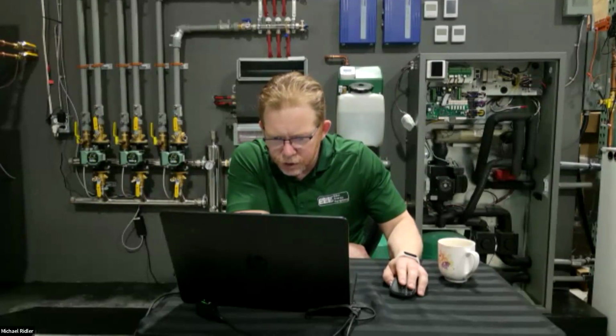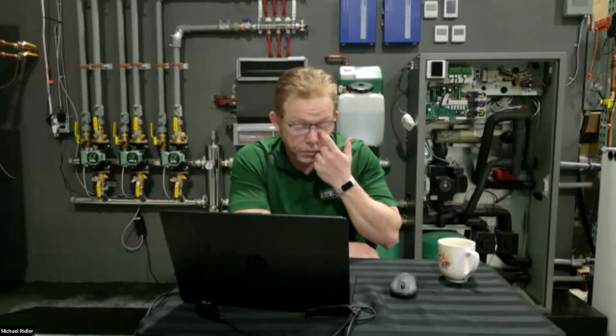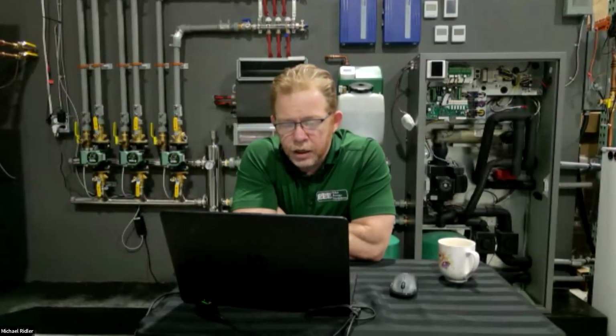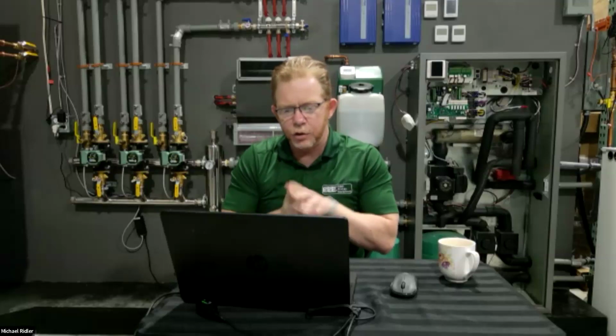So could you pipe them together for a higher ultimate COP? Yes, you absolutely could. There's a project being worked on right now, not my project, where they're taking two thermal batteries—one at 58 degrees and one at 43 degrees—and putting them together to maximize the overall COP of the heat pump by having two different temperature PCM batteries.